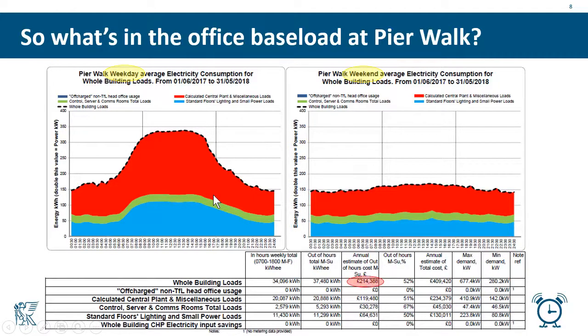The scary bits are annual out of hours. So our out of hours is essentially any time from this vertical line around 6 o'clock on a weekday through to about 7 o'clock in the morning, and all of the weekend, right? Okay, Pier Walk does have one floor that has a contact center in it, so there is an element of one quadrant on one floor that does run out of hours, but that's how we measure all of them. 200,000 pounds, 240,000 pounds a year here, and the scary numbers are the kilowatts: that central plant, whatever it's been commissioned to do, and the BMS is letting run, a minimum demand of 140 kilowatts, and the floor lighting and power, this blue stuff, 80 kilowatts.